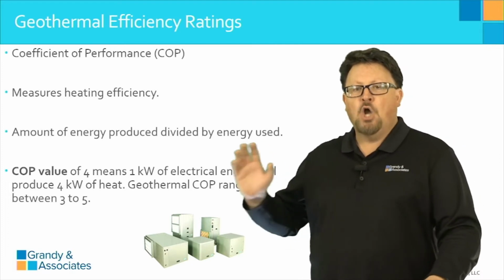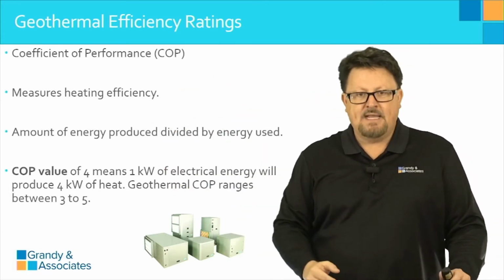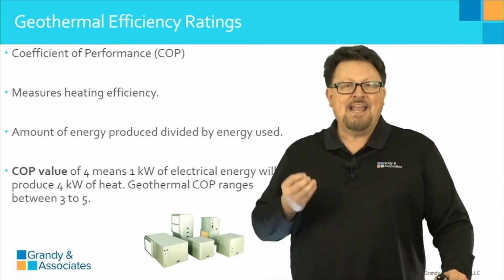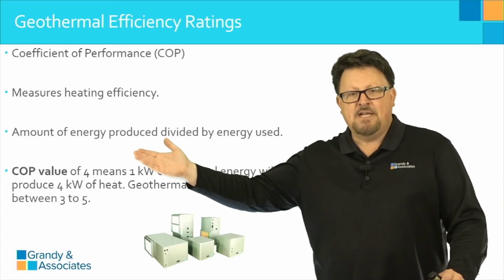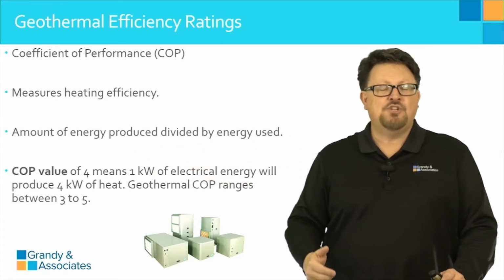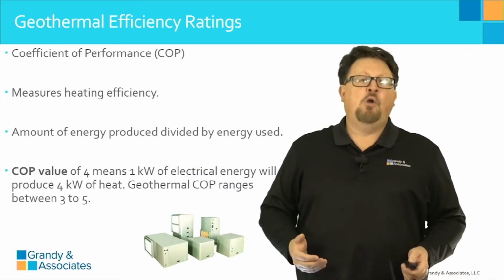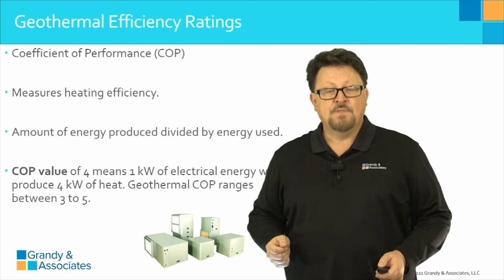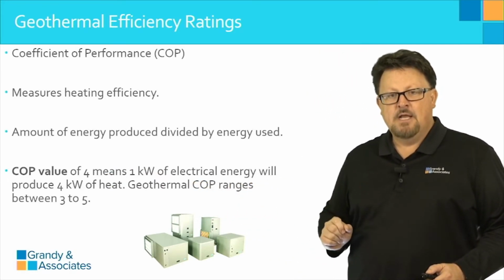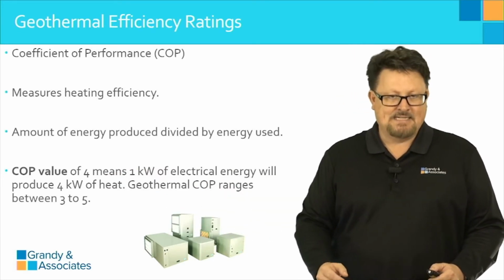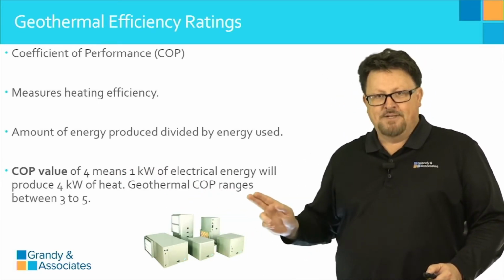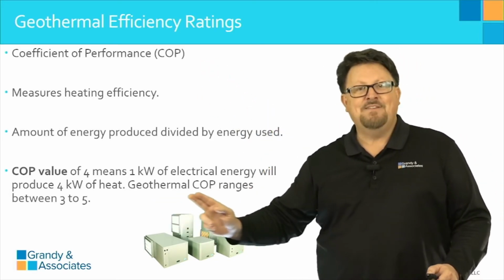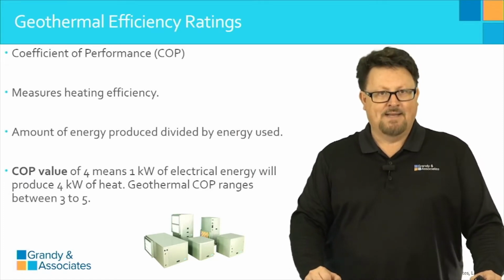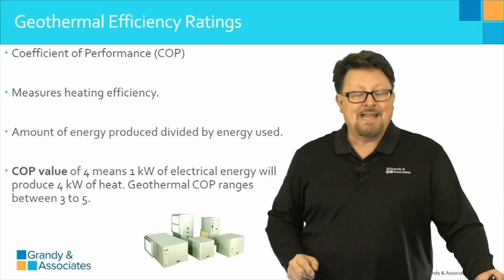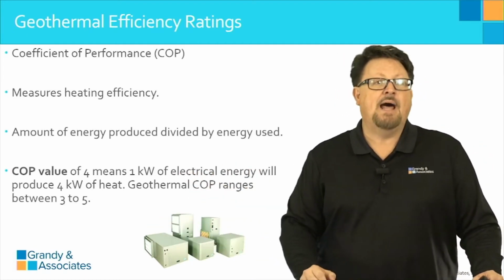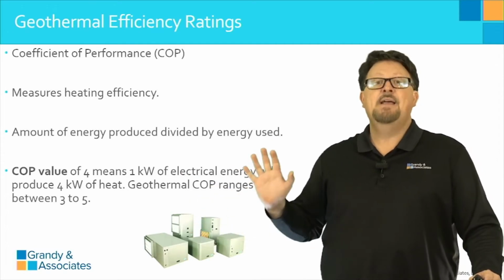Coefficient of performance, or COP, is a measurement of heating efficiency. It is the amount of energy produced divided by the energy that is used. For example, a geothermal unit with a coefficient value of 4 means that 1 kilowatt of electrical energy will produce 4 kilowatts of heat. Not too bad. Geothermal ranges in this particular metric between 3 and 5, which is where most geothermal systems are going to land. Heat pumps in general will also show up in this metric, but it is also something specifically applied to geothermal systems. So that's very solid and very good.